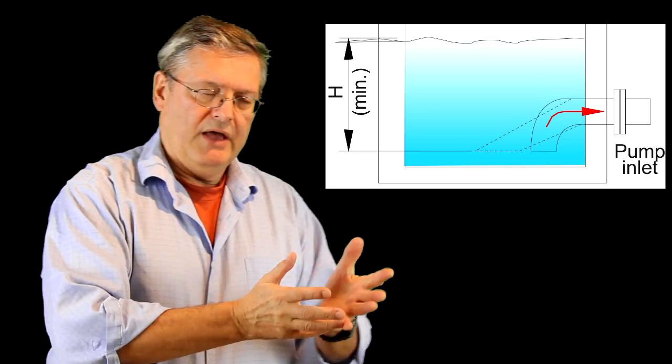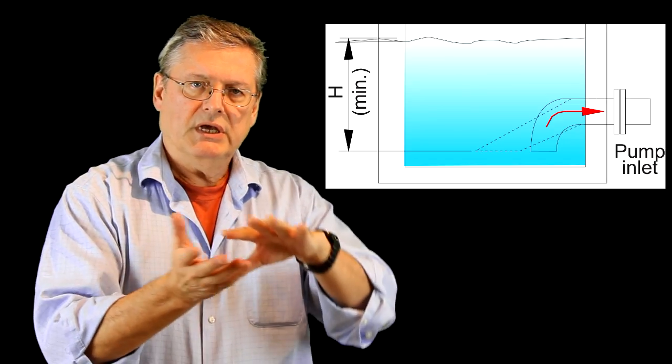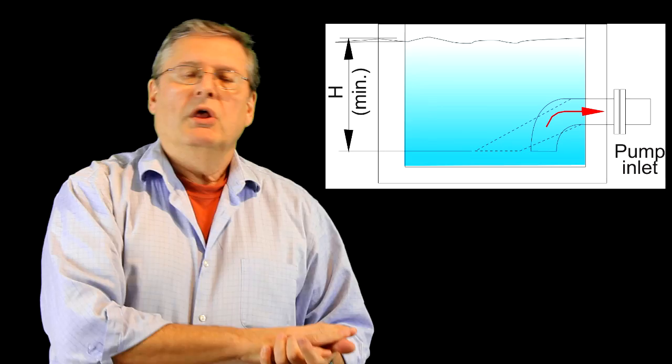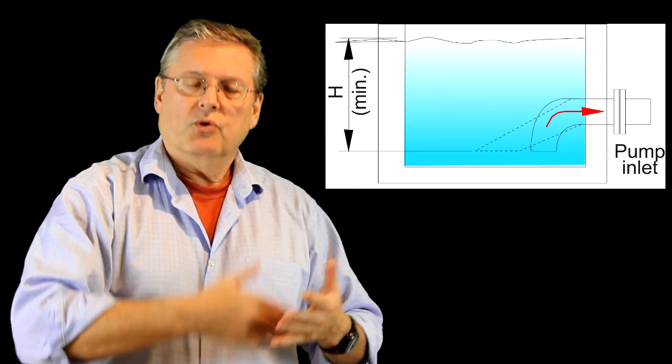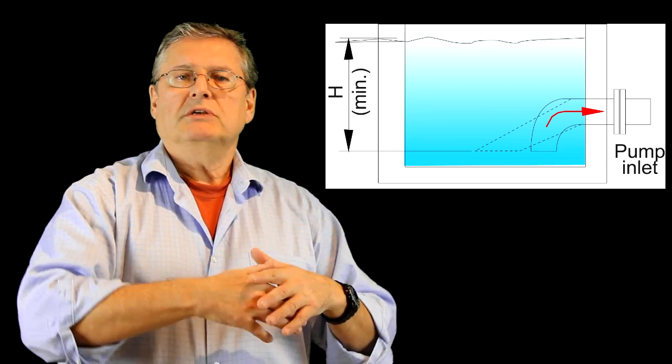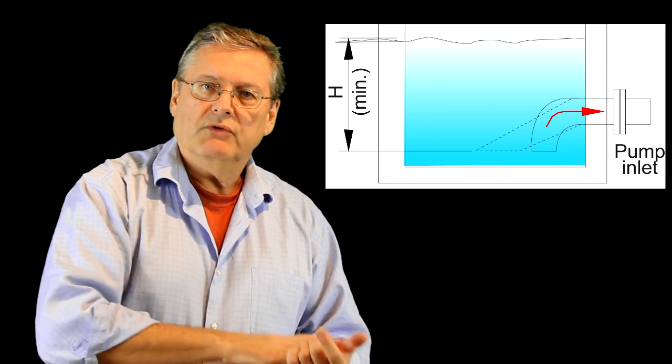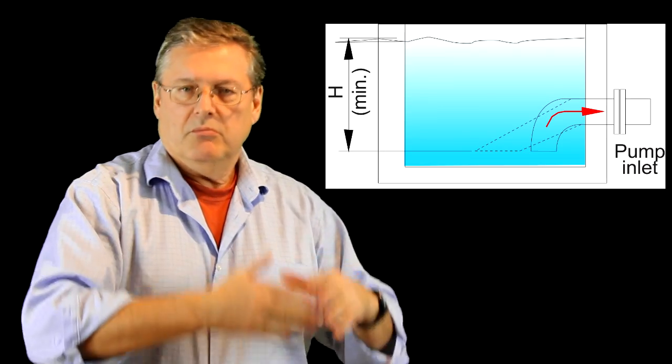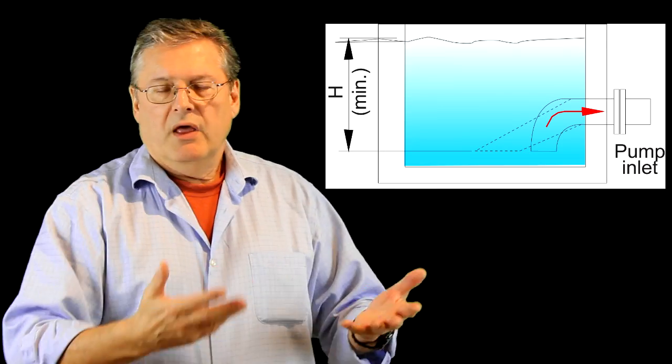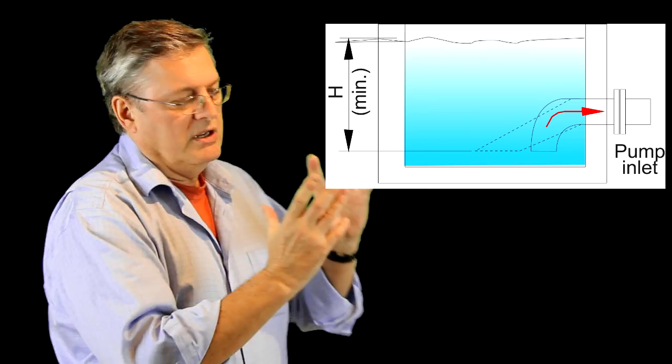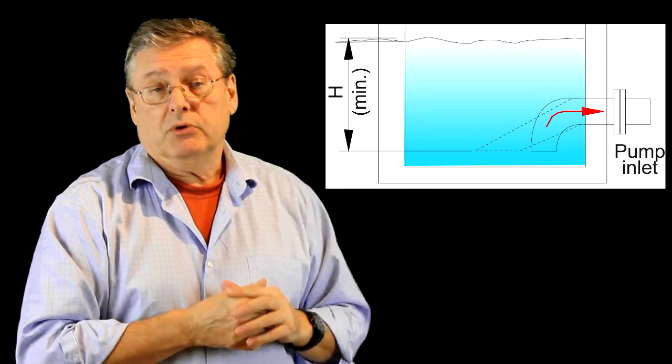The elbow has a big advantage in that the bottom of the elbow is lower, so we're getting greater submergence. This will help us avoid vortexing and we'll be able to empty that tank to a much greater depth than otherwise. The slanted is a compromise and the straight in would be the most economical.